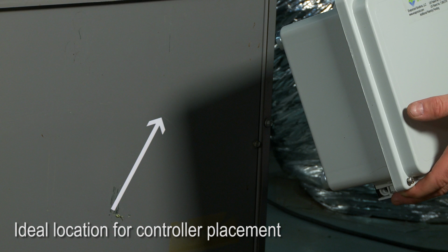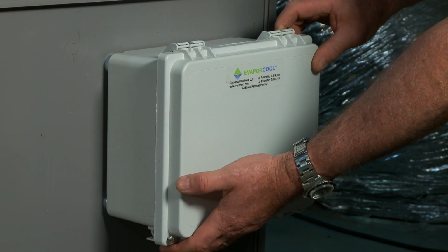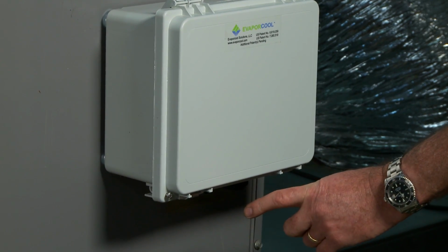Next, find the location for the Evaporcool controller box as indicated in the Evaporcool system layout diagram. Make sure the location identified has enough surface area for the magnets of the controller box to attach to, and that the box is easy to access. Place the box on the outdoor unit with the connections facing down.